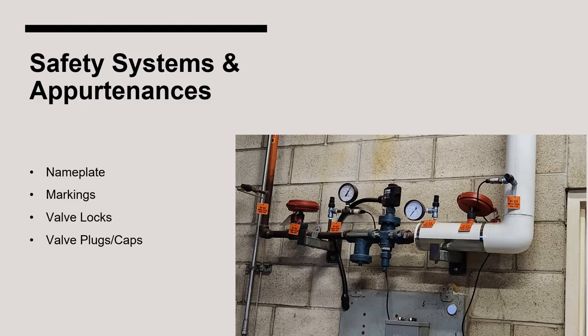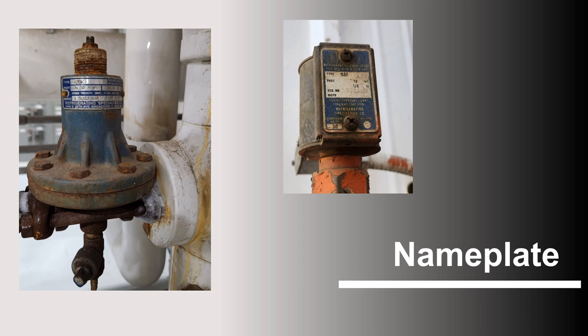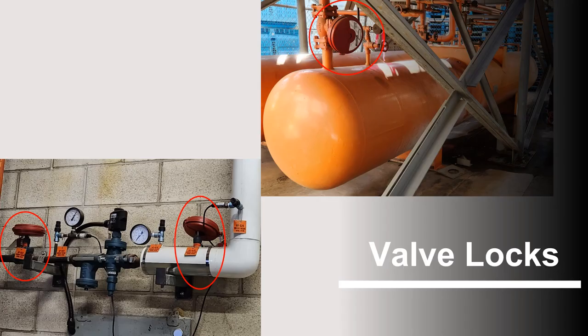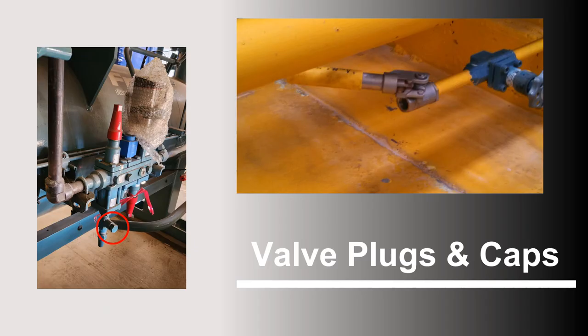We will review nameplates, markings, locks, plugs, and caps as they relate to refrigeration valves. Valves have either adhesive or metal nameplates fastened by welds or rivets. Valve bodies are required to be marked with the manufacturer's name or symbol, direction of flow if applicable, model number, size, and range limits. IIAR Standard 3 allows for size and range limit markings to be omitted due to space restrictions. Valve locks are used to secure valves in an open or closed position, preventing unauthorized personnel from changing the setting. Plugs and caps are used to mechanically seal a section of pipe or valve opening shut.